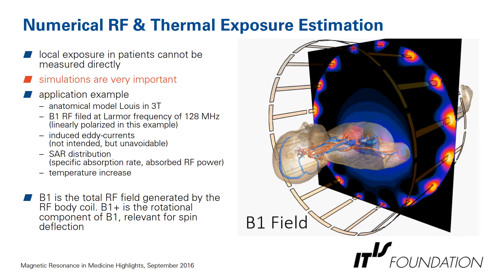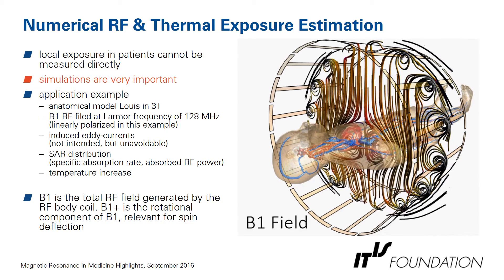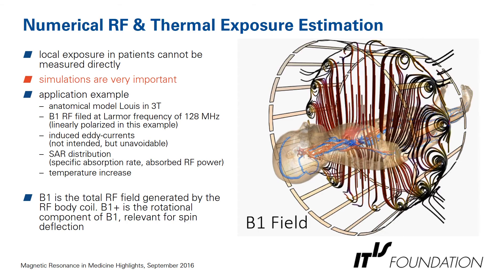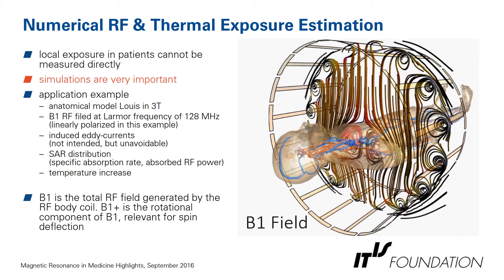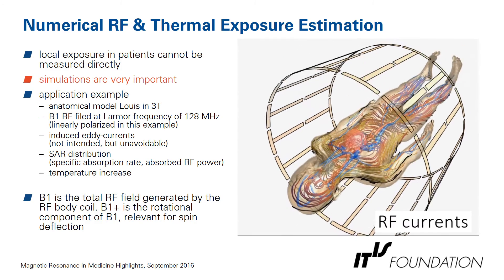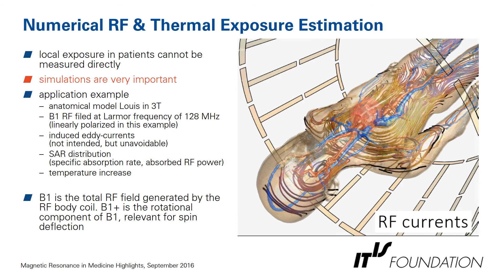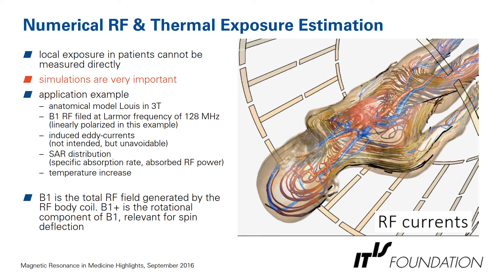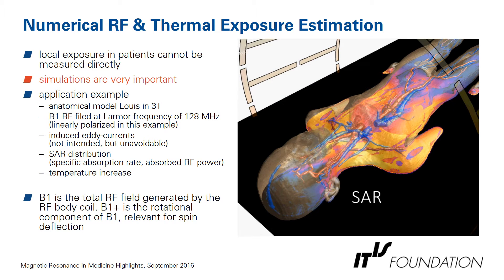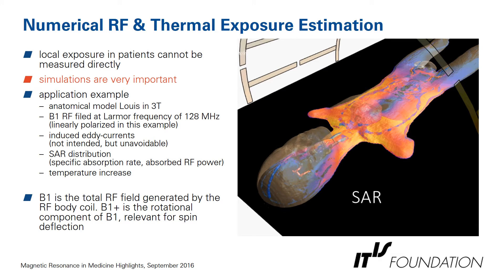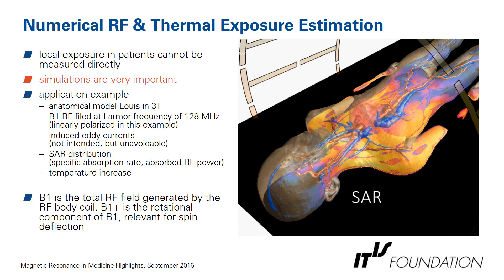This is with the anatomical model Louis in a 3 Tesla birdcage coil. What you see now is the B1 field — it's a linearly polarized field, and this is the one responsible for spin deflection, so for imaging. However, if we have a varying B field that induces eddy currents, these are not intended or wanted, but they're unavoidable — so we have to deal with them. They're circular and increase with radial distance from the center.